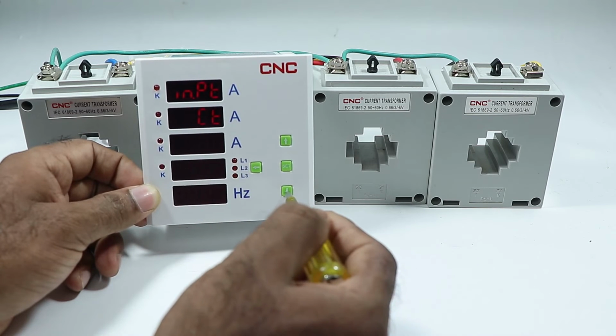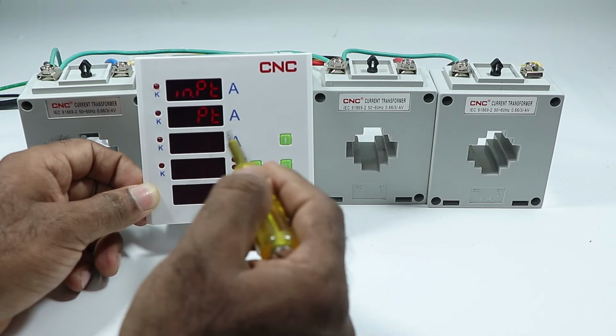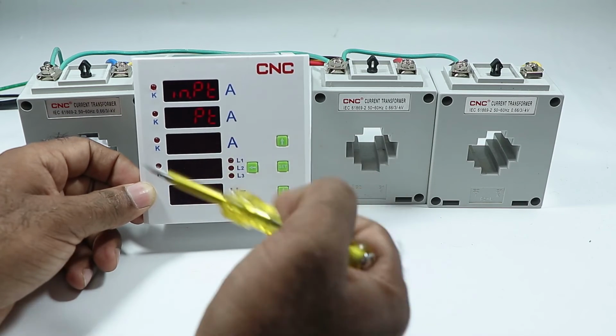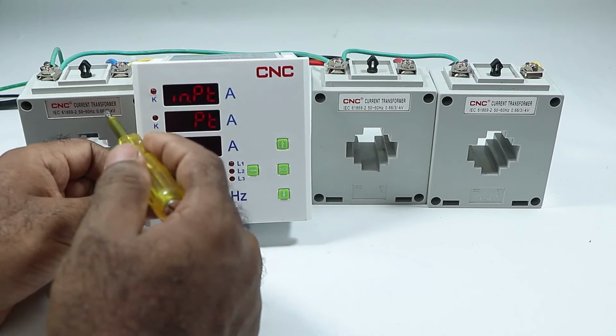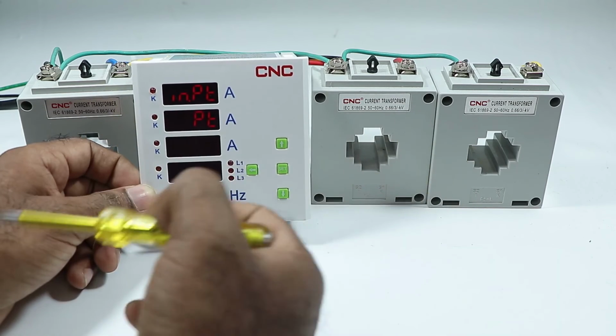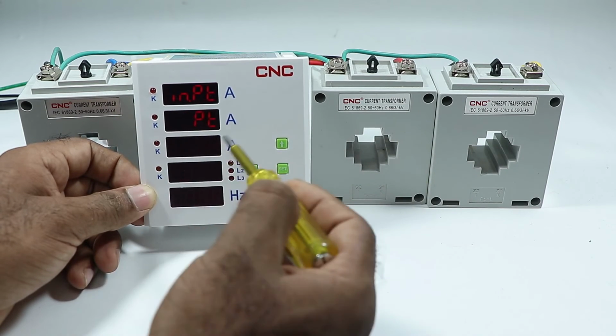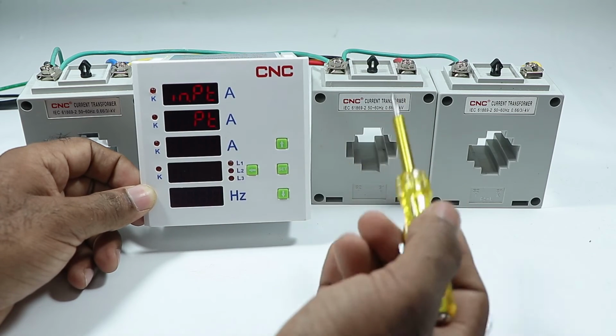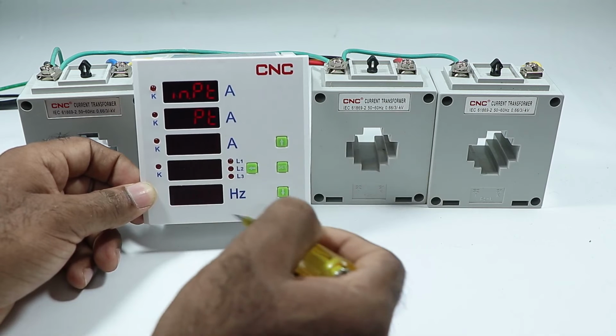After setting this, when I press the button again, PT is written here. What is PT? For measuring current we use CT. Similarly, for measuring voltage, a potential transformer is used. If you use a potential transformer with this meter, you have to program for this also.